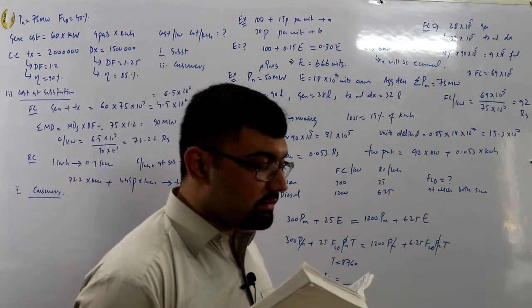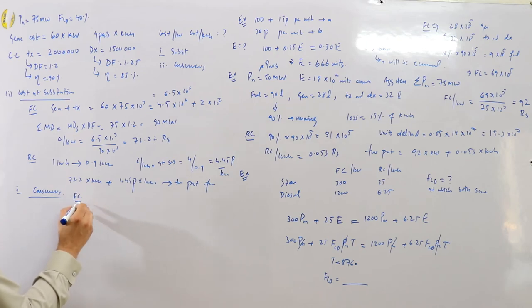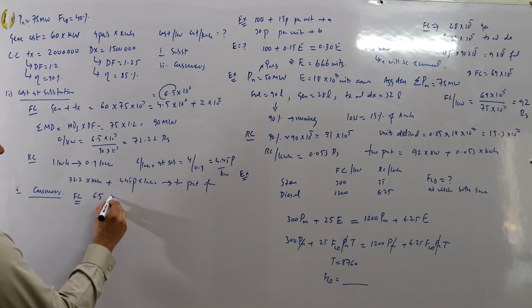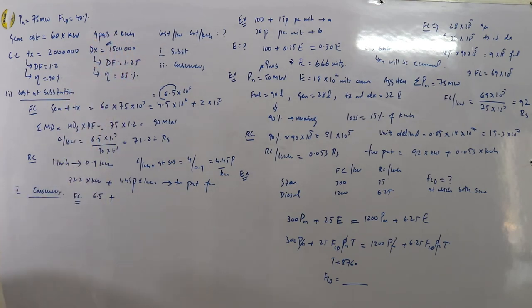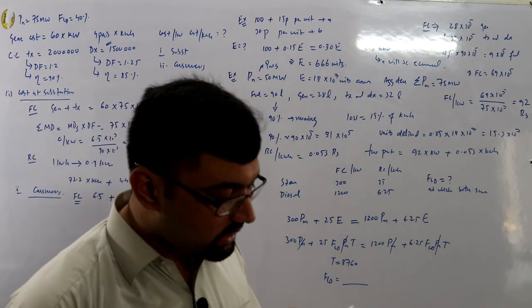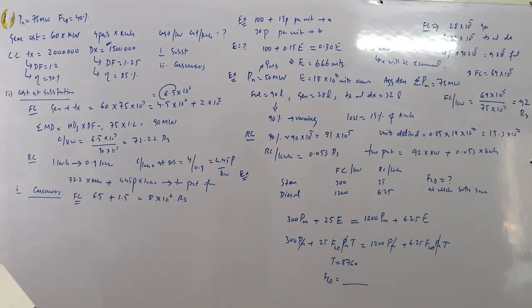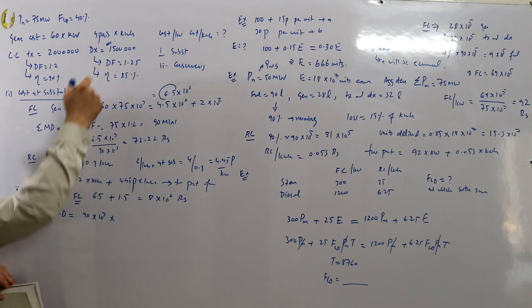For consumer premises: total annual fixed charges = substation fixed charges (6.5 × 10⁶) plus distribution cost (1.5 × 10⁶) = 8 × 10⁶ rupees. Aggregate maximum demand of consumers = 90 × 10³ × 1.25 = 112.5 × 10³ kilowatts.